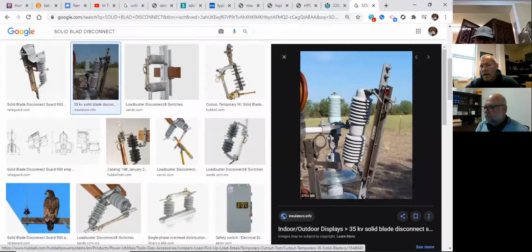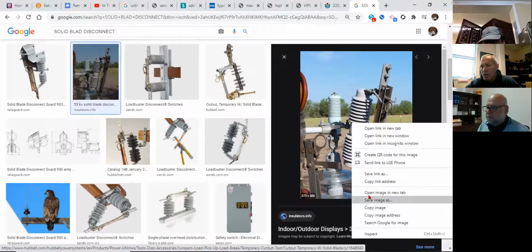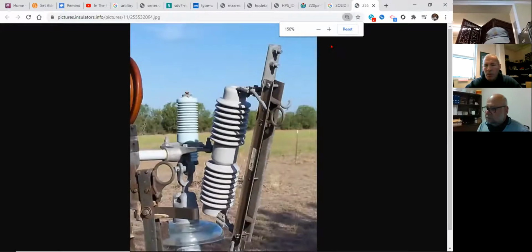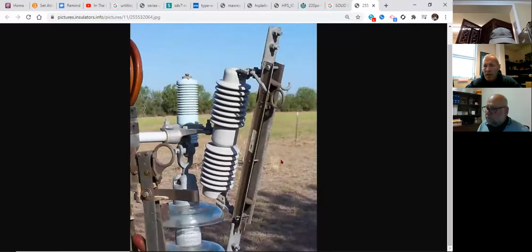Some of these come pre-built, like this. This is actually an attachment that you can put on a cutout. So this has been modified on this switch here to include a dead blade in it. It's a normal switch that we use, but now it has a dead blade in it. And it's made of what? Solid copper, with silver connections at the connection points. This is not line protection. If you have something solid in between the two, it is not line protection. We have to have a fuse or some other means to have line protection. So that's the definition for dead blade.